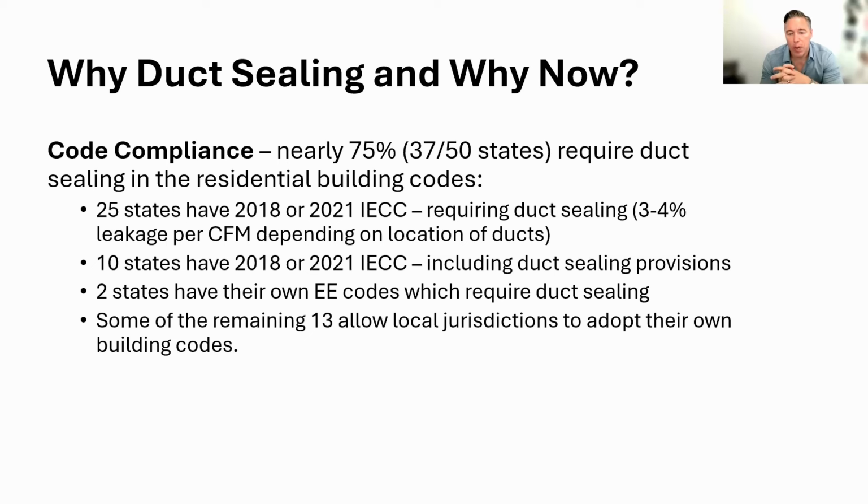But what we're seeing over and over again is this is one area that our builders, contractors, everyone seem to struggle with. For those of you who've been testing ductwork, I'm sure you've seen failures. Aeroseal has been a big factor for us. Increasingly we're just going straight to sealing, not driven by us, but by our contractors because they're tired of trying to meet these 3 and 4% standards, and they've come to know the total cost of actually installing this ductwork is less when they're using Aeroseal to both test and seal that ductwork.